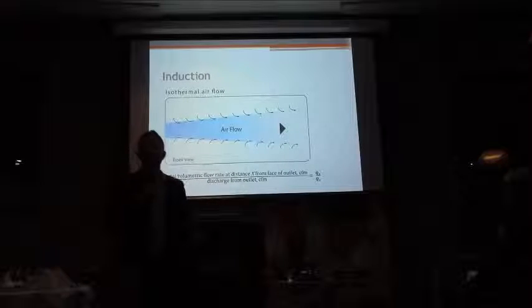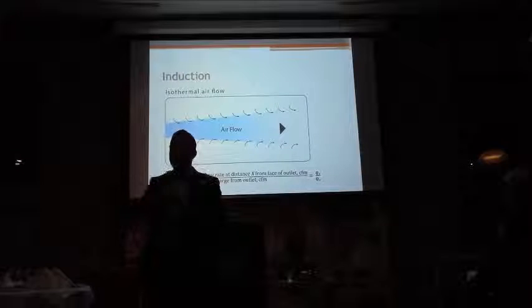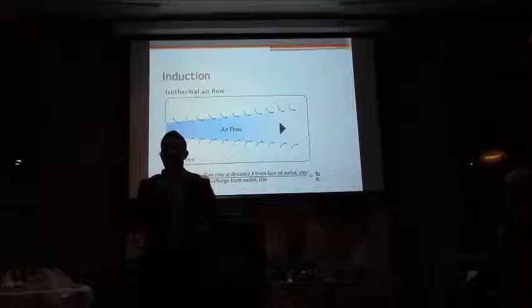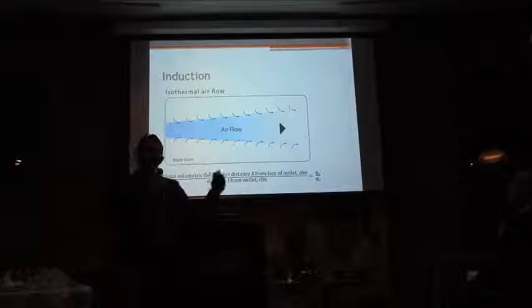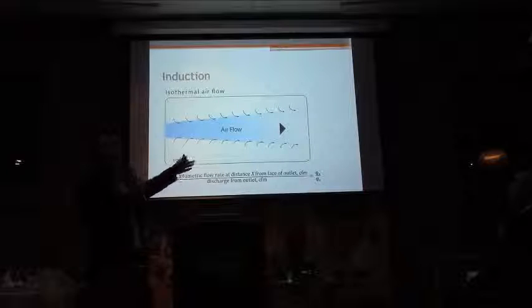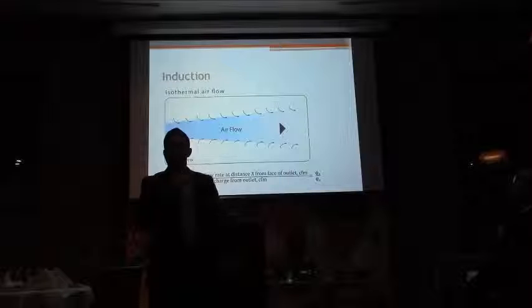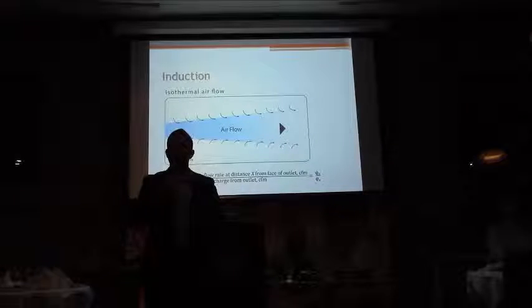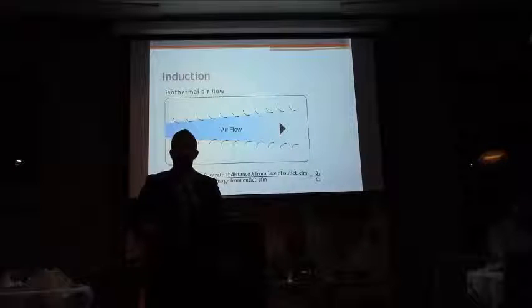The higher your induction ratio, the more you get room air mixing. The advantage is that you have a lower temperature gradient across the room. There are two advantages to that: you're more comfortable because everybody in the room feels the same temperature. If I'm standing here and somebody's standing at the other end of the room, we're going to feel the same temperature. But also there's not going to be any temperature gradient vertically, so you're not going to have cold feet, and I mean that literally. The formula is that the induction ratio is your total volumetric flow, induced plus primary, divided by your discharge from the outlet, your primary air. A standard diffuser, like any cone diffuser, like these diffusers right here, has an induction ratio of 4. That means for each CFM delivered through the diffuser, there are 4 CFM of room air being induced by your primary air. A high induction diffuser has an induction ratio of 17. So you have much more induction, and that's going to allow us to have better comfort and ultimately energy savings.